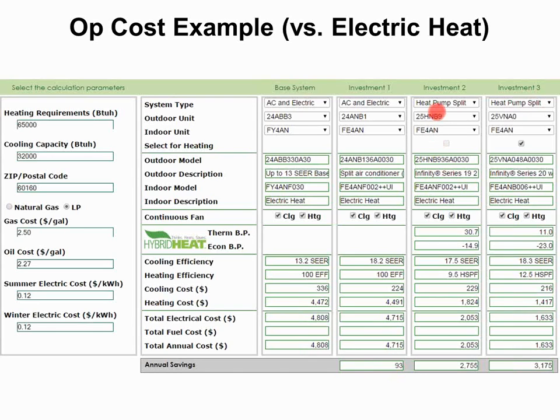I could put in a hybrid system, a heat pump split system that has a fan coil, a heat pump, and electric resistance supplementary heat, and now they're going to save $2,700, right? They've cut their bill by more than half. If I put the variable speed heat pump in with electric backup, and I do that little upsizing thing to go to the 4-ton, they're going to save almost $3,200.